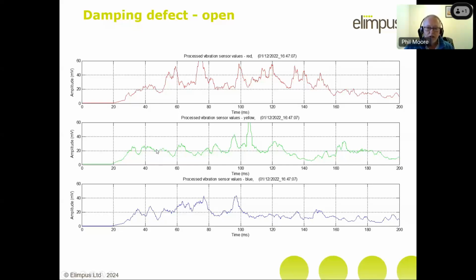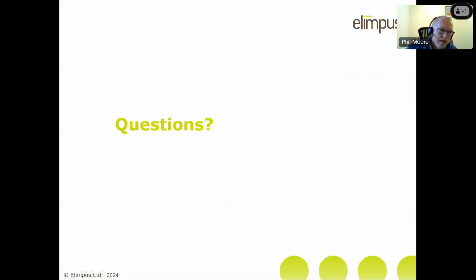And what you shouldn't see is what we're seeing here, where there's suddenly a large increase in the vibration. Probably what's happened there is that the damping is starting to become slightly less effective, so it's now creating another vibration within the circuit breaker, and that obviously needs to be resolved, otherwise it'll shake itself to bits. Okay, so I think that's me finished, so back to you, Martin, if we want to take some questions.